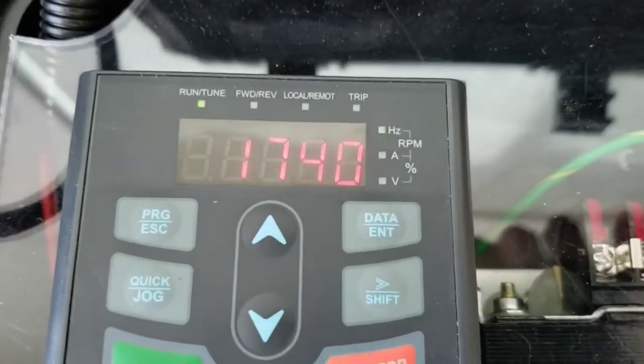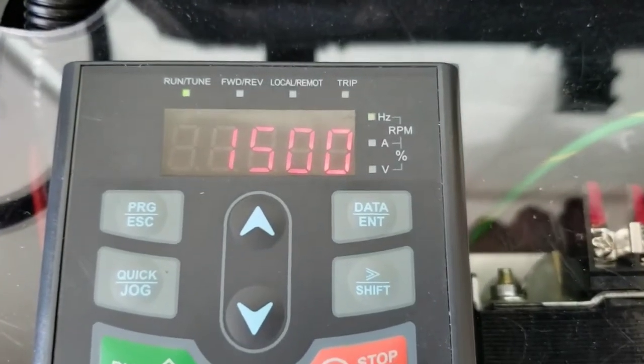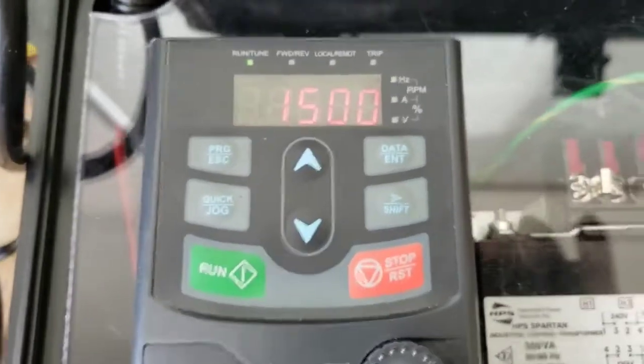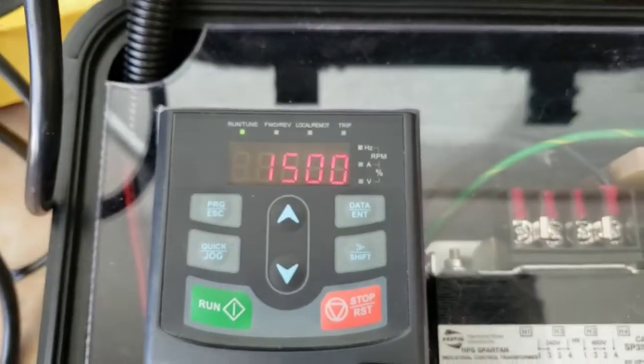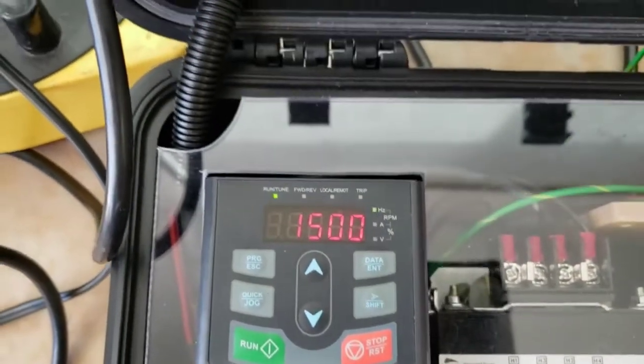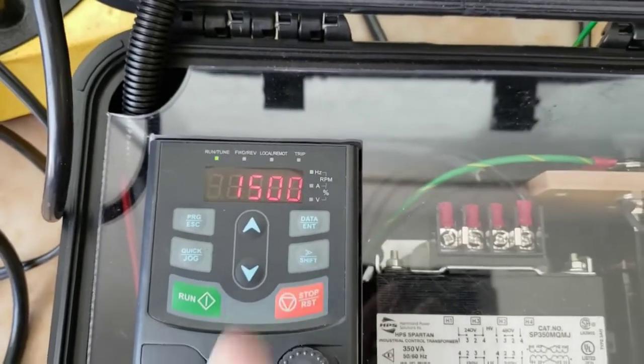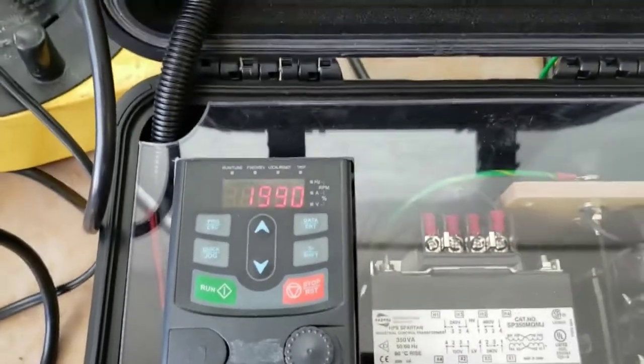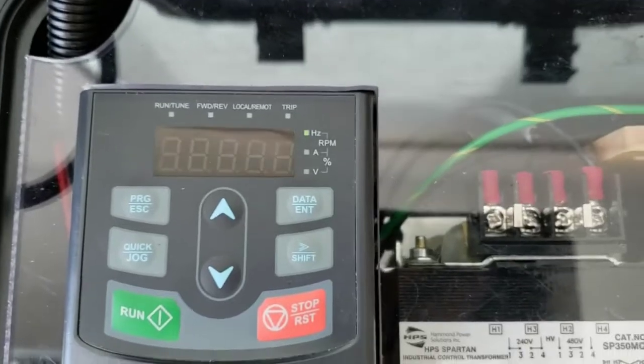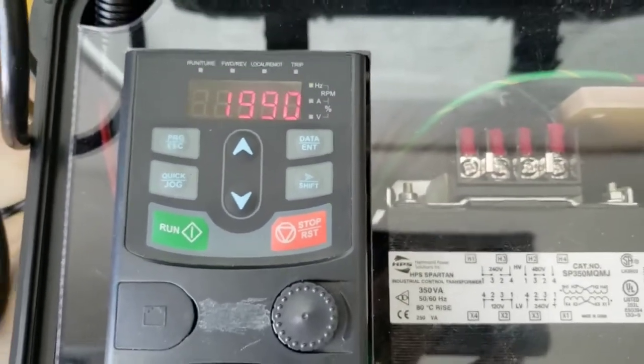See, now that it got done with its sweep, it dropped down to the minimum frequency because we're getting arcing. It's clearly a failed cell, so that would give you a good indication. So the sweep is a nice test. We'll stop when we're done. See, that one found a resonant frequency for that cell at 1990 hertz, which is clearly way out of the range that we're expecting. So that's an indication that we've got a failed cell.